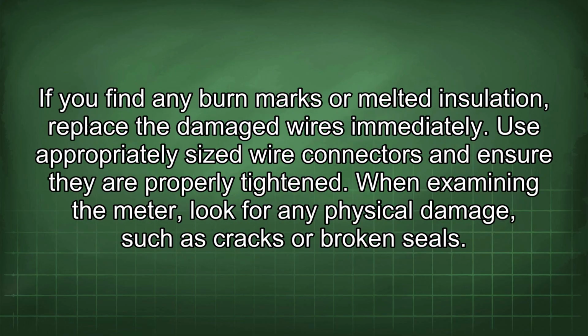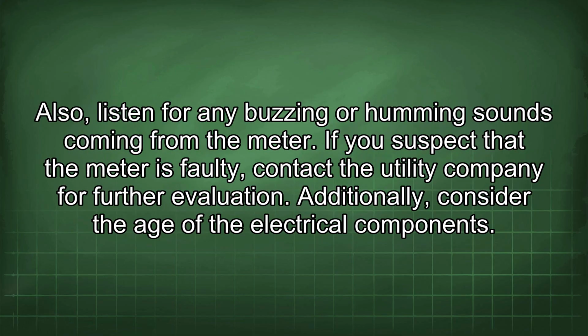If you find any burn marks or melted insulation, replace the damaged wires immediately. Use appropriately sized wire connectors and ensure they are properly tightened. When examining the meter, look for any physical damage, such as cracks or broken seals. Also, listen for any buzzing or humming sounds coming from the meter. If you suspect that the meter is faulty, contact the utility company for further evaluation.